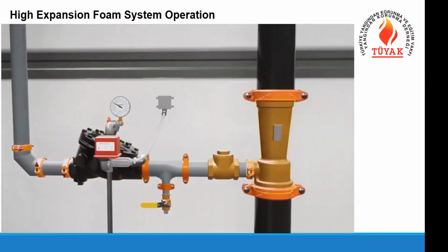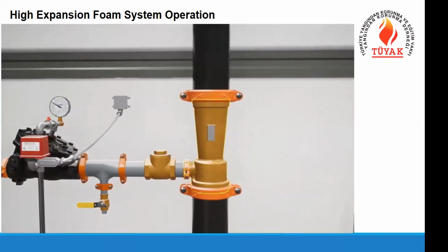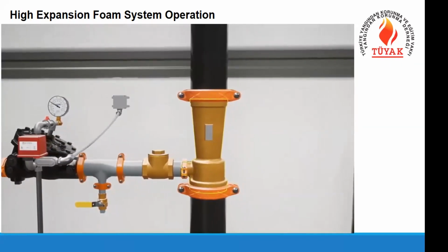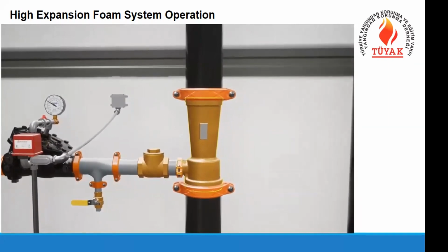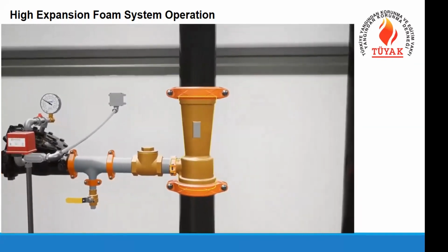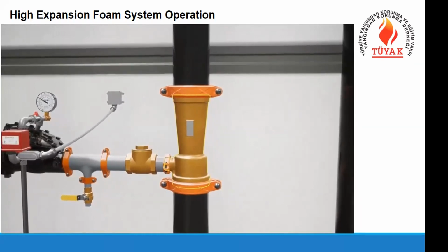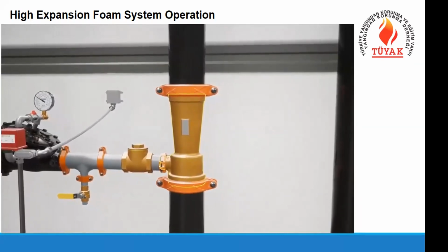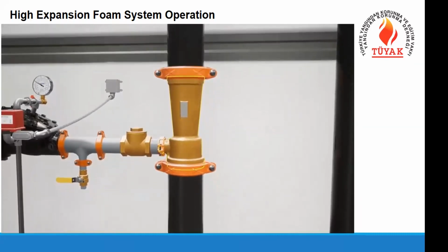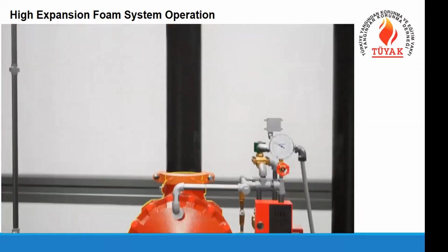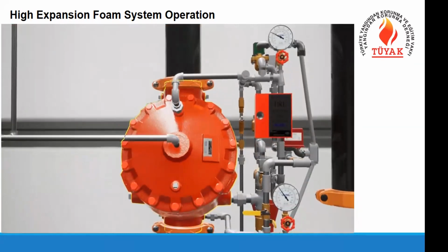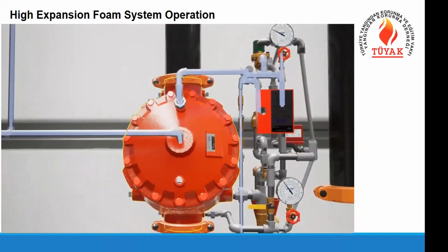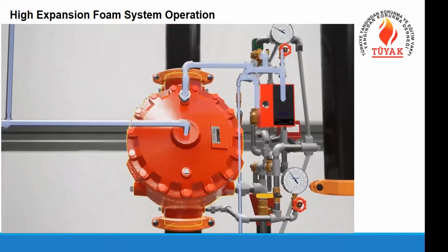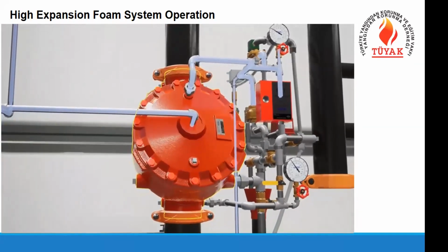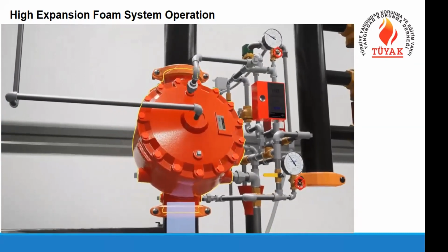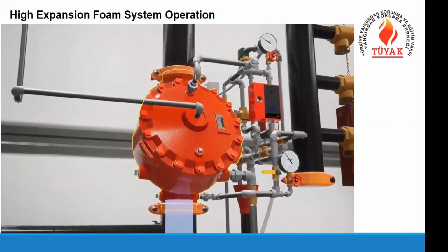Continuing past the concentrate control valve is the ratio controller. A ratio controller is a proportioning device that meters foam concentrate into a water stream to create a foam water solution, typically at a 3% ratio, depending on which foam concentrate is used. Upstream from the ratio control valve is the F1 deluge valve, which has a shared priming connection with the concentrate control valve. This allows the two valves to activate simultaneously. The deluge valve is holding back the main water supply until the system is activated.